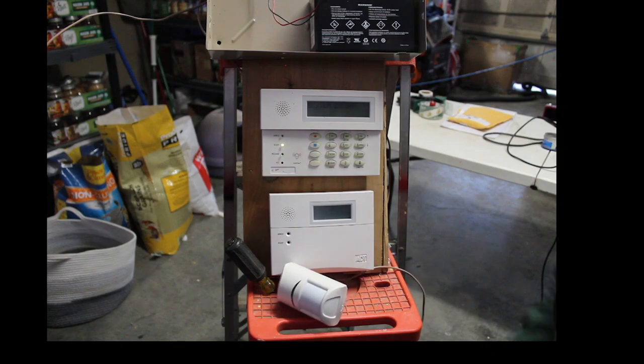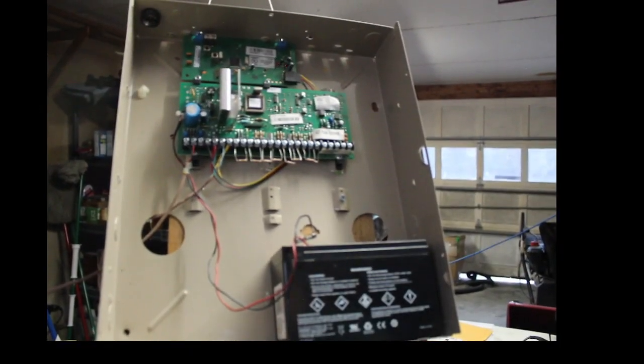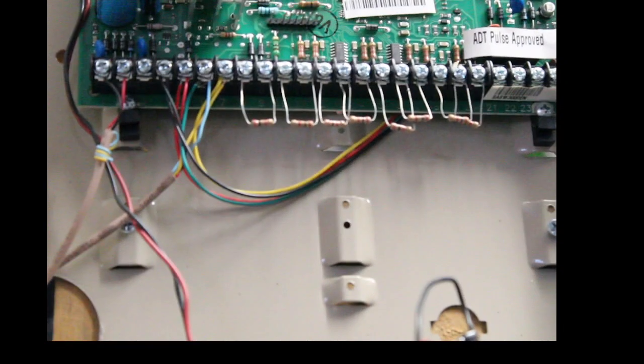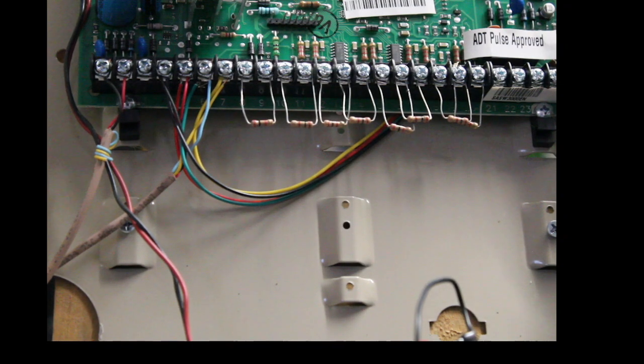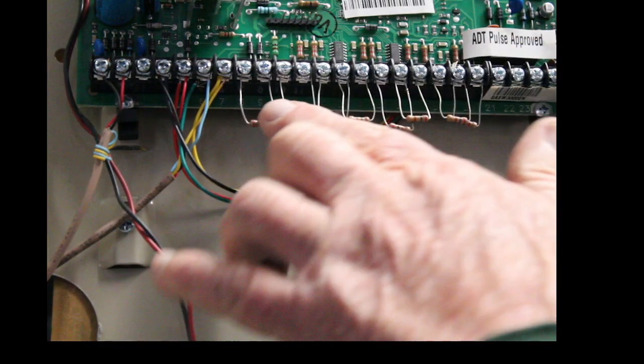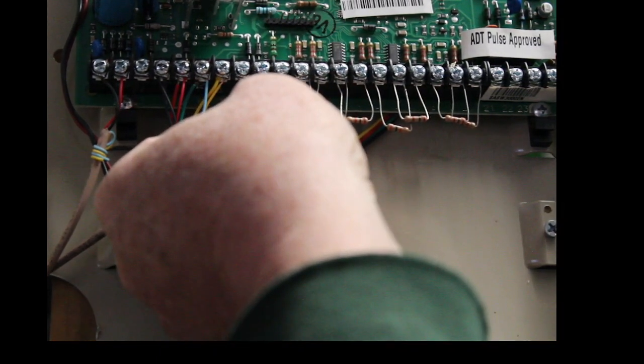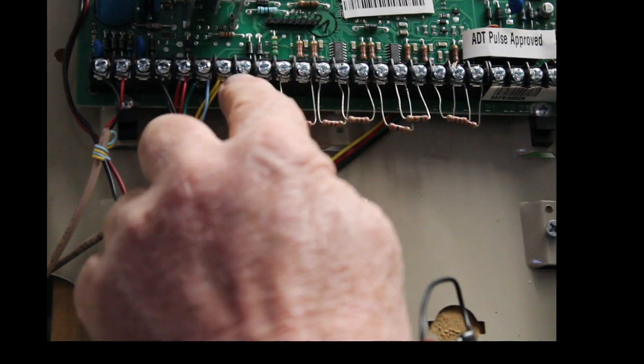I'm going to wire mine in just for simplicity into zone one. You can wire it into any one of these zones. And then all you do is just, you've got a resistor right here. Just take the resistor off, and then put the yellow and blue back on to one of these two, where you took the resistor off. So, let me take my resistor off. Then you take the resistor. I've got to get some more wire on here.